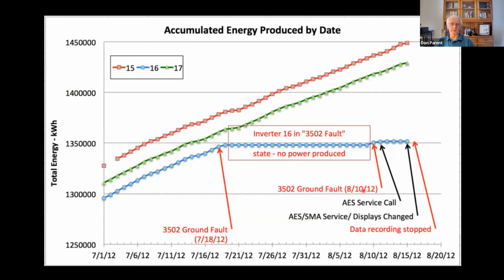And they called the service company, the installer. And the installer came out and they realized there's a problem on the roof. So they actually went up on the roof to find out why there was a ground fault. What was the cause? Now, again, there are over 2,000 panels working with one inverter. There's a lot of connections involved there, and every one of those needed to have been evaluated. But it doesn't look like that happened.